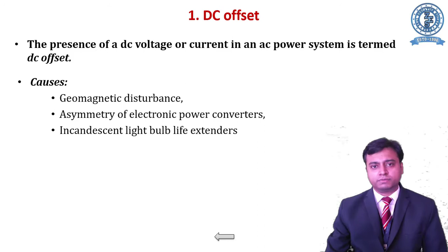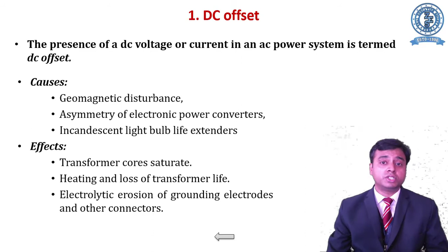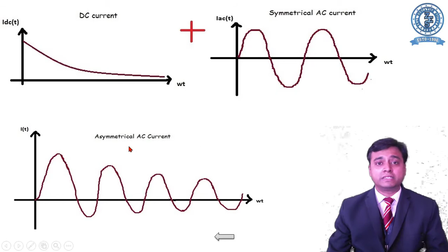What are the effects because of that? Your transformer core will saturate, it will heat up, it might blow up, it will be burned off. So these are some problems which occur because of the DC. There could be a rusting effect or electrolytic erosion which will happen in the grounding electrodes. So these are the problems which will be created by DC offset. Now how does DC offset occur? You can see here, the DC current mixes with the AC, and the waveform which we finally have will be an entirely different waveform, that is an asymmetrical waveform.